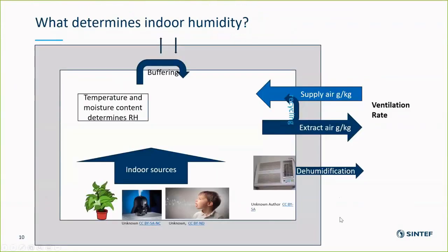Indoor humidity is determined by the sources indoors. Supply air contains moisture, and extract air removes moisture. Some of that moisture can be recycled. The mass balance will also be mediated by buffering in materials, and the mass balance and temperature together will determine the relative humidity. It's possible for moisture to diffuse in or out of the building, but that's not really of importance in practical situations we have encountered so far.